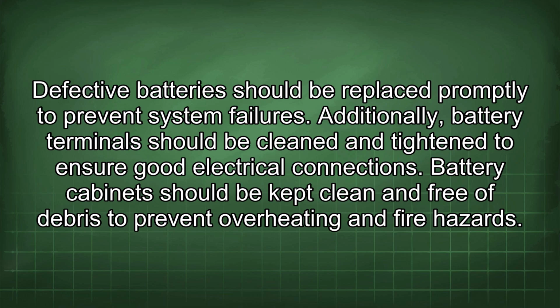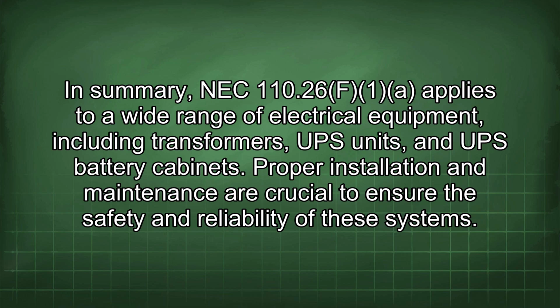Additionally, battery terminals should be cleaned and tightened to ensure good electrical connections. Battery cabinets should be kept clean and free of debris to prevent overheating and fire hazards. In summary, NEC 110.26 applies to a wide range of electrical equipment, including transformers, UPS units, and UPS battery cabinets. Proper installation and maintenance are crucial to ensure the safety and reliability of these systems.